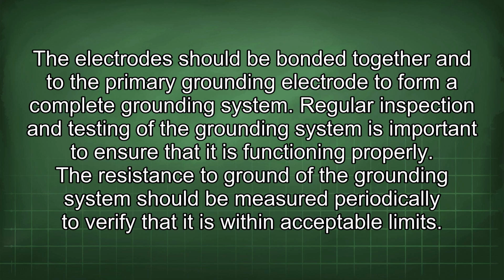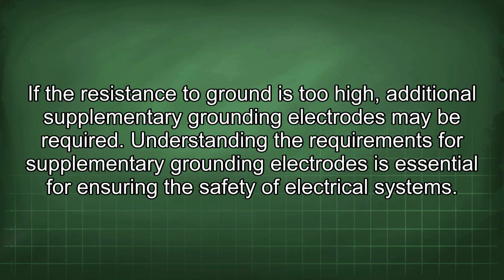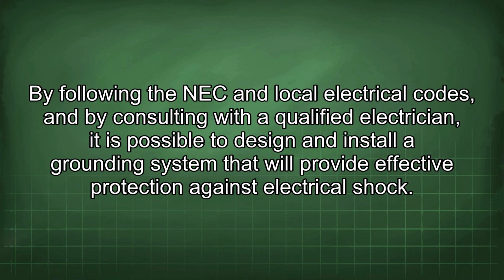The resistance to ground of the grounding system should be measured periodically to verify that it is within acceptable limits. If the resistance to ground is too high, additional supplementary grounding electrodes may be required. Understanding the requirements for supplementary grounding electrodes is essential for ensuring the safety of electrical systems. By following the NEC and local electrical codes, and by consulting with a qualified electrician, it is possible to design and install a grounding system that will provide effective protection against electrical shock.